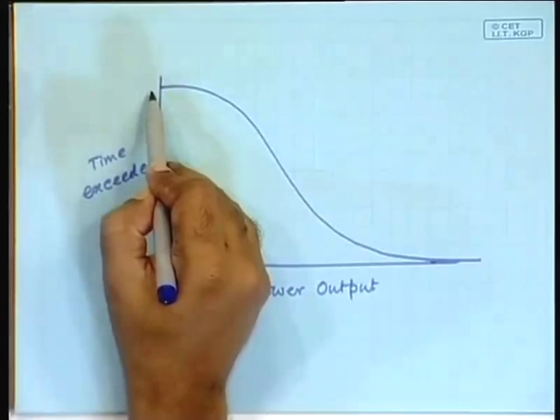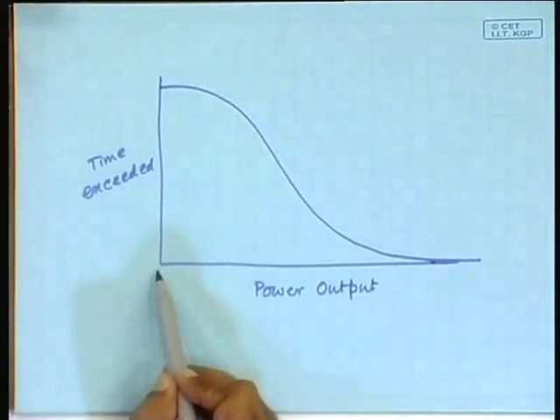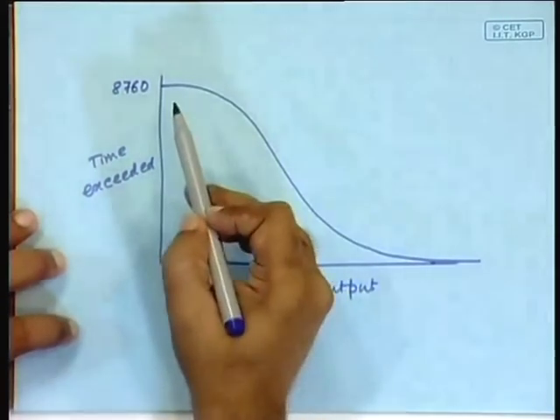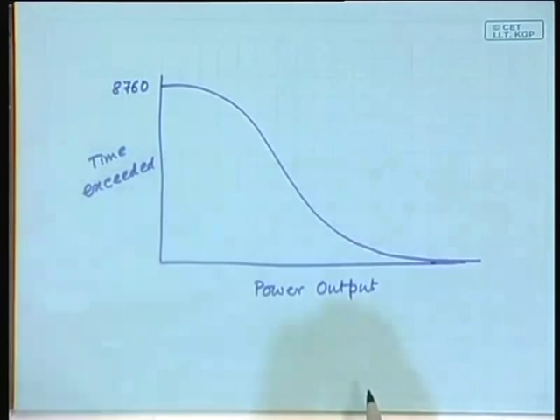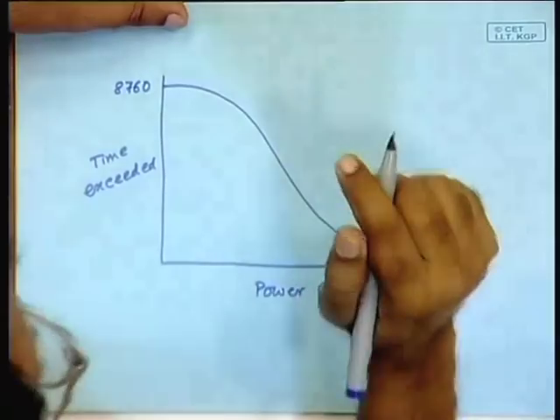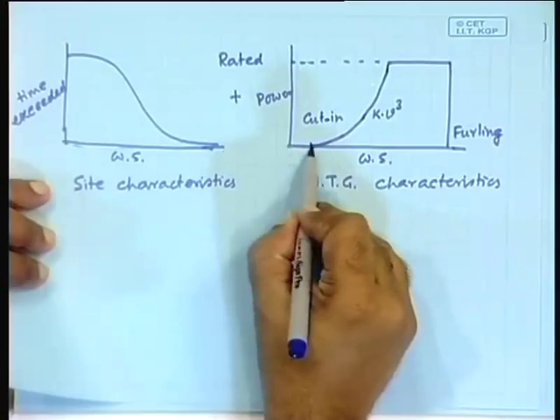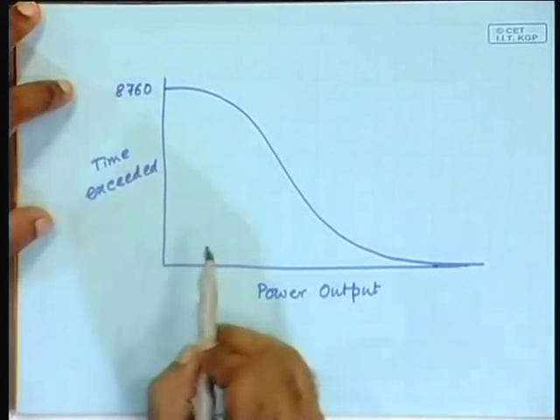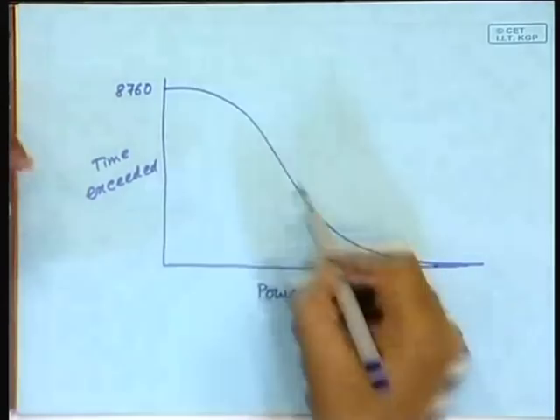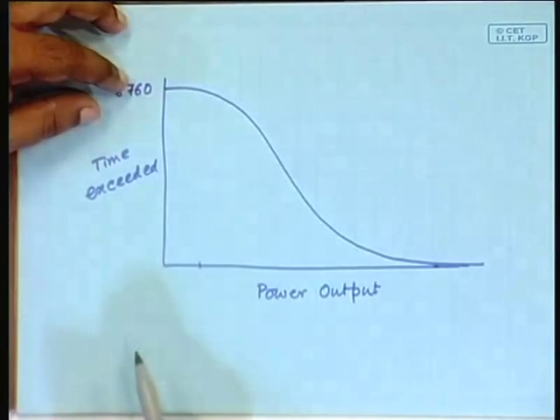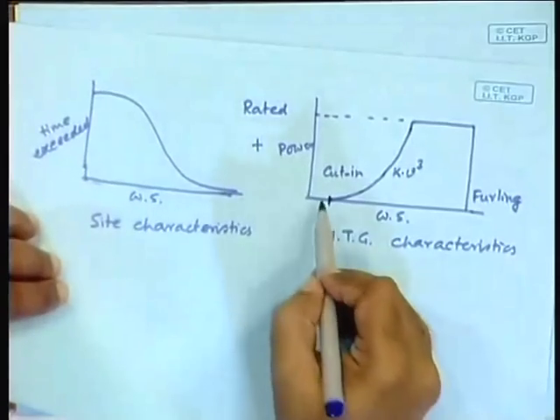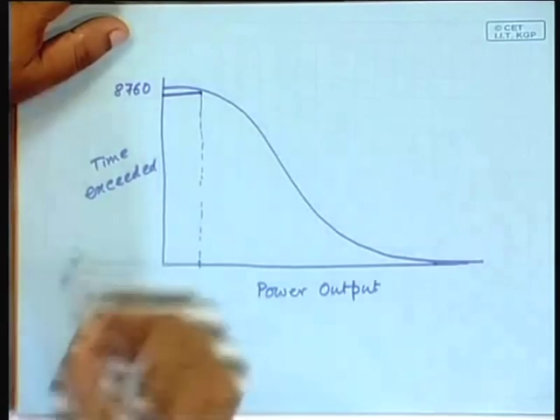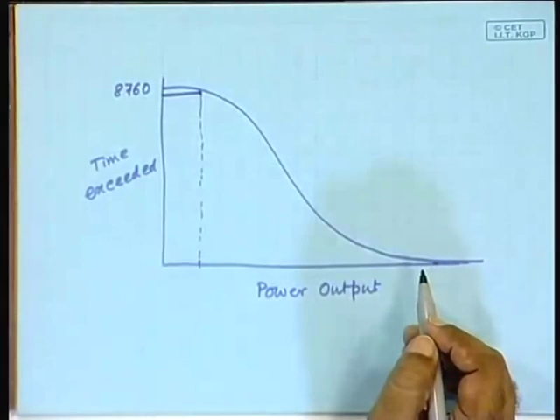This point represents the total number of hours in a year, since zero power is exceeded for 8760 hours. Out of this whole time, power generation is really zero below the cut-in wind speed. So some part will be chopped off — you will not get power output there, corresponding to a low value of power. When cubed, a small velocity gives a particular point, and below that you are generating nothing. So this part gets chopped off — you are not generating in this region.